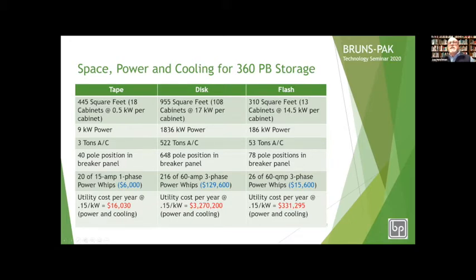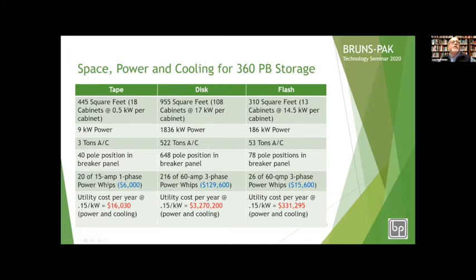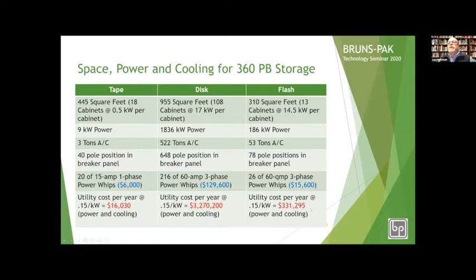Back to the numbers: 445 square feet for tape, 955 for disk, and only 310 for flash. Power: 9 kW for tape, 1,836 kW for disk, and 186 kW for flash. Air conditioning: 3 tons for tape, 522 tons for disk, and 53 tons for flash. Breaker panels: 40 pole positions for tape, 648 for disk (about 15 and a half panels), and 78 for flash. Power whip costs: 20 single-phase 15-amp whips at $6,000; 216 three-phase 60-amp whips at $130,000; and flash at $15,600. At 15 cents a kilowatt: $16,000 a year for tape, $3,270,000 for disk, and $331,295 for flash.